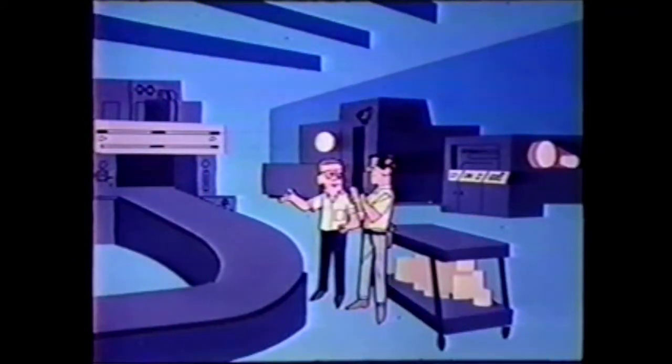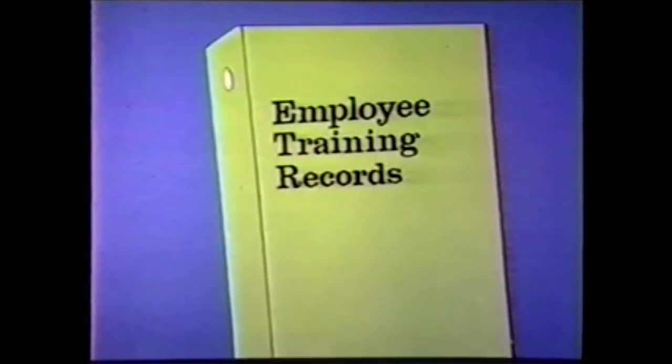The employer shall provide training to all employees to ensure that purpose and function of energy control are understood, knowledge and skills for safe application are received, and usage and removal of energy control are understood. The employer shall certify that employees' training has been accomplished and is being kept up to date. The certification shall contain each employee's name and dates of training.